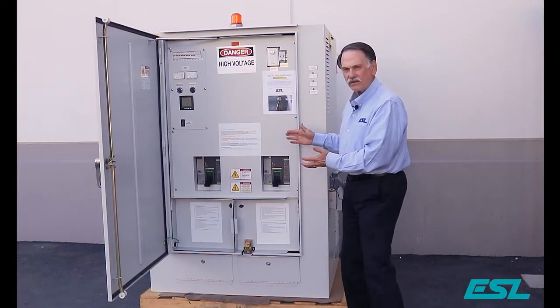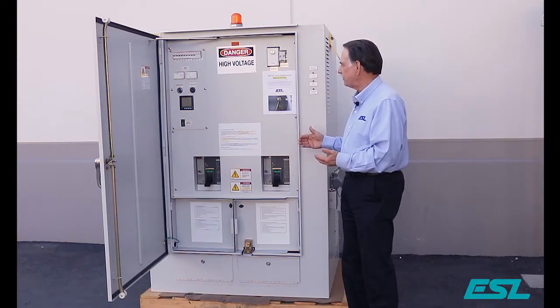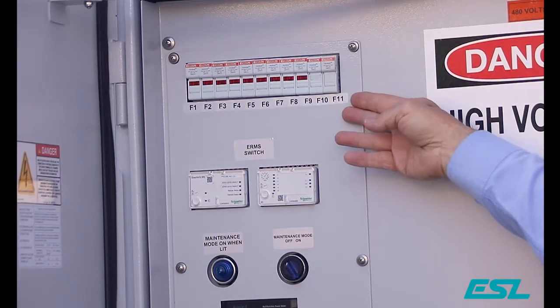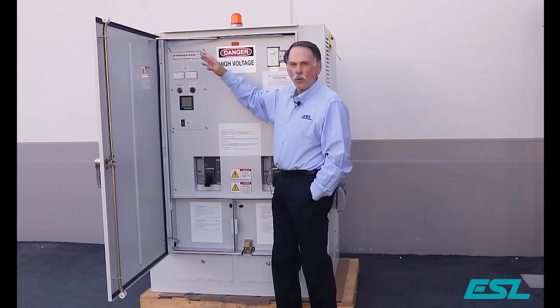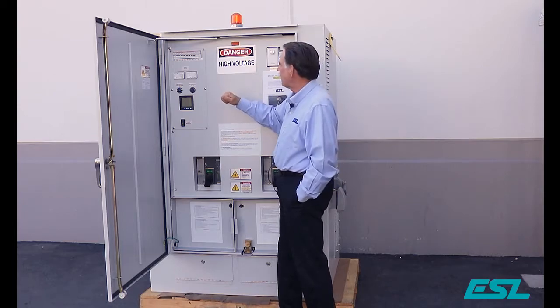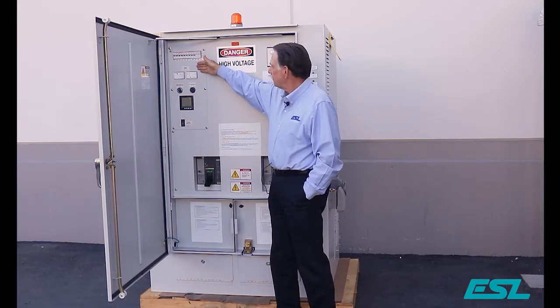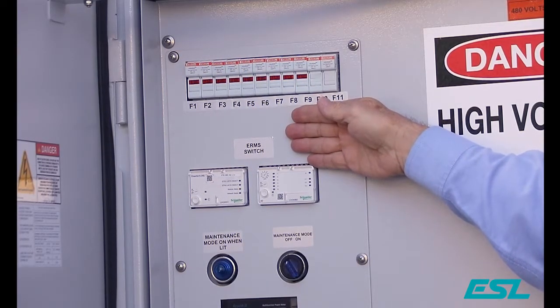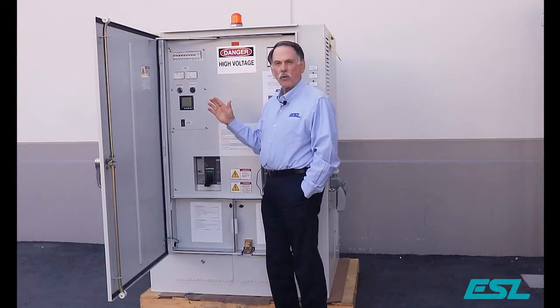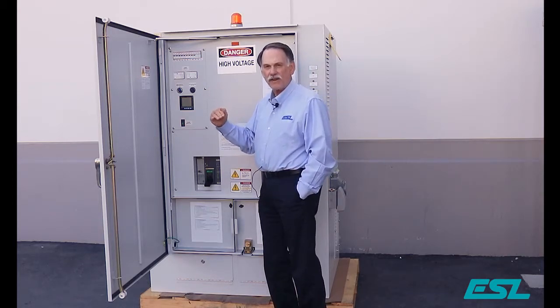The dual purpose docking stations, like all ESL units, can come with a number of optional features. We have a number of fuses that we can provide depending on what options and requirements you have for your particular application. For units with 1200 amps or higher breakers, we have an ERMS switch. This is an energy reduction maintenance setting so that 1200 amps or above breakers can be set back to reduce the arc flash capability.